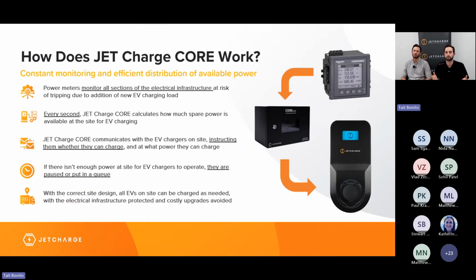So now I'll talk about how JetCharge Core actually works and what's going on under the hood within our load management system. So it all starts with power meters. Power meters are installed throughout the main switchboard or the electrical infrastructure to measure the power draw throughout that infrastructure. And so they're required at any section of the electrical design that is at risk of tripping due to the new EV charging load. So you might be adding that 250 amps to the 1000 amp supply, noting that the 1000 amp supply is at risk of tripping. So you need to add a power meter at that 1000 amp supply to record how close to approaching that limit the power draw at the building is.